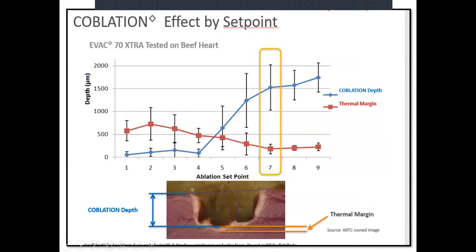Blue denotes coblation depth — as you increase settings you can see increasing lesion depth, and collateral thermal damage increases accordingly. The take-home message: if you're operating on a child or in the nose, using settings of five or six will not give good results. It's only from setting seven onwards that you start getting good lesion formation.